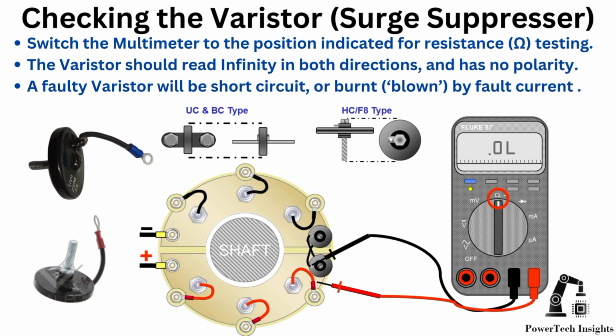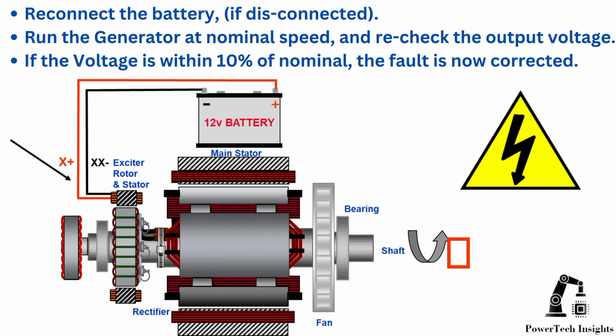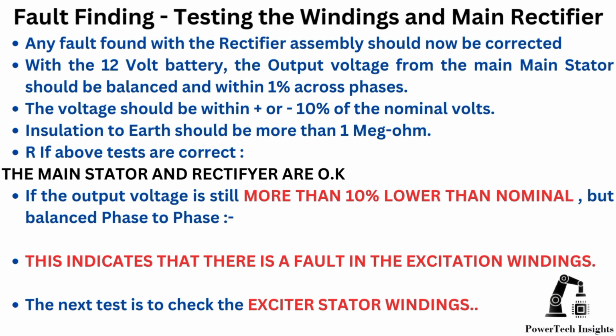Checking the varistor. Switch the multimeter to the position indicated for resistance, ohm testing. The varistor should read infinity in both directions and has no polarity. A faulty varistor will be short circuit or burnt by fault current. Fault finding, testing the windings and main rectifier. Reconnect the battery, if disconnected. Run the generator at nominal speed and recheck the output voltage. If the voltage is within 10% of nominal, the fault is now corrected. Any fault found with the rectifier assembly should now be corrected.